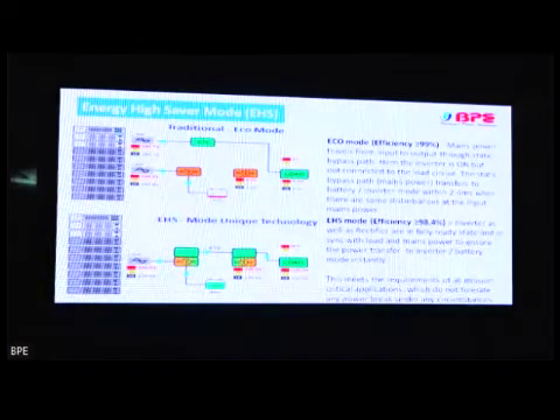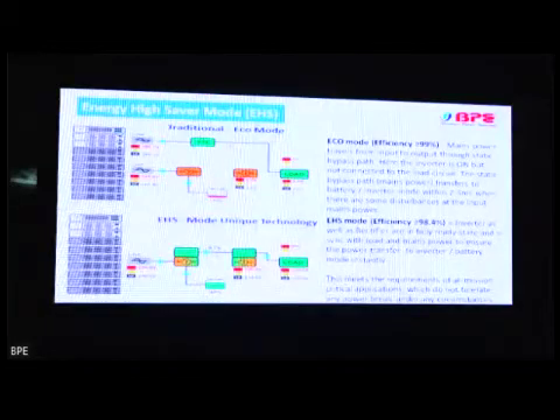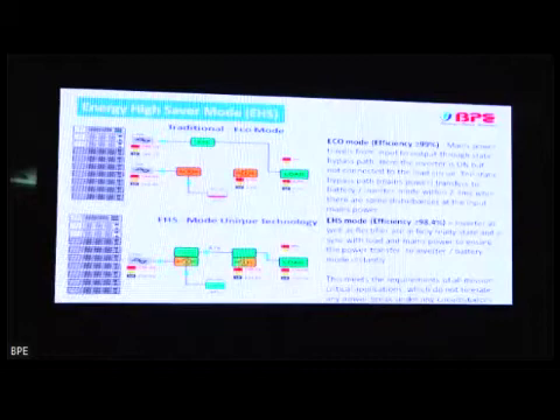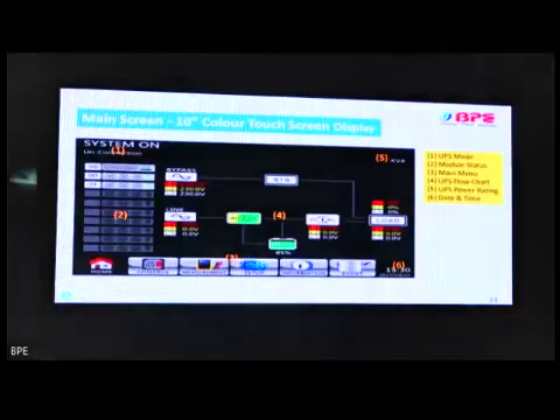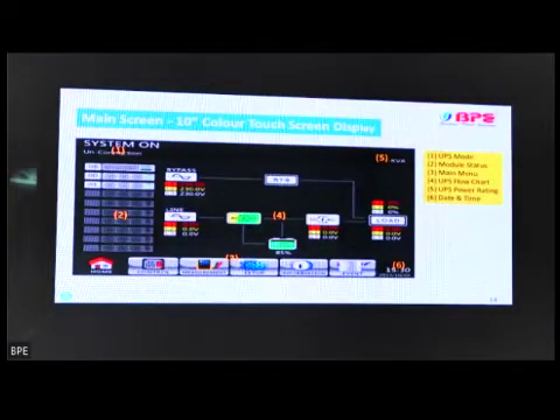This is the EHS mode, where one is the eco mode. Actually, there are two types of mode. One is the eco mode. In eco mode, the UPS works on the bypass mode, the 99%. And in EHS mode, there is a separate mode where your rectifier and inverter always work in sync with the load and mains power. If everything goes wrong, then it automatically shifts to online mode, and it will give you the very high efficiency of 98.4%.